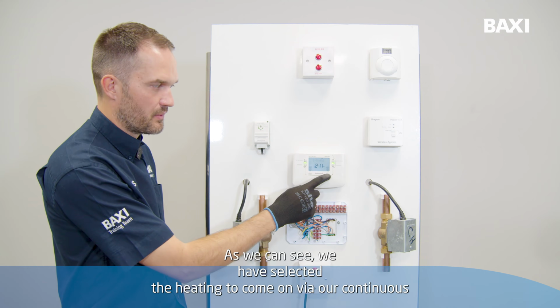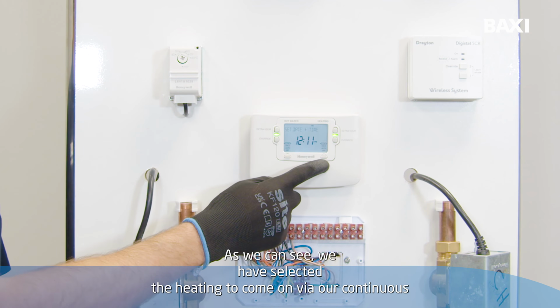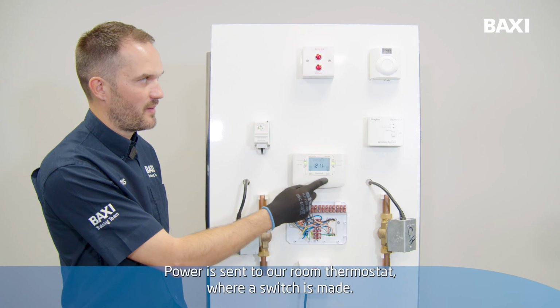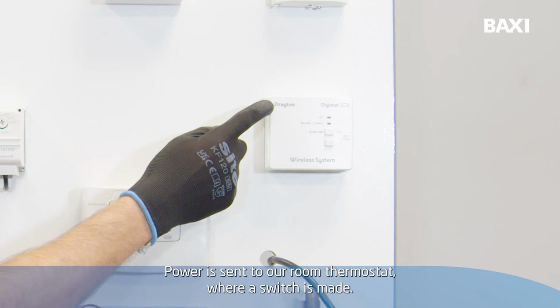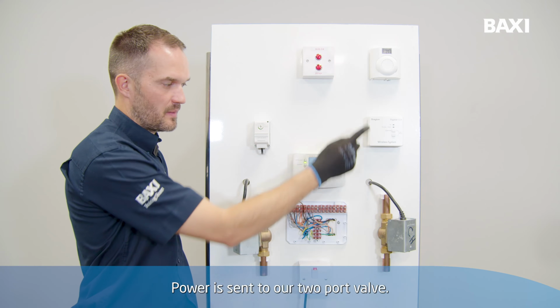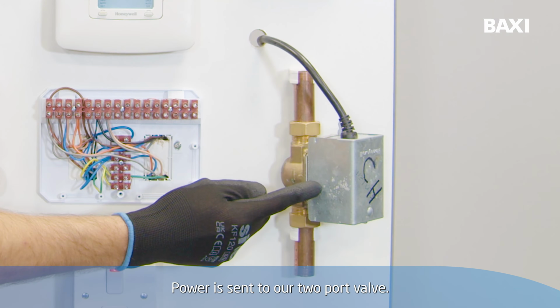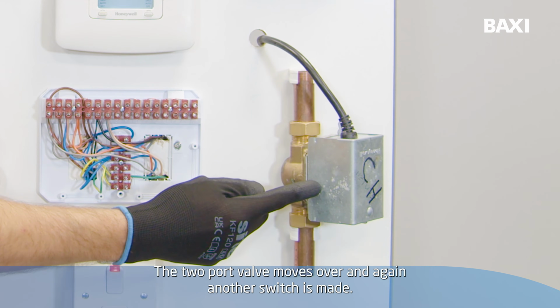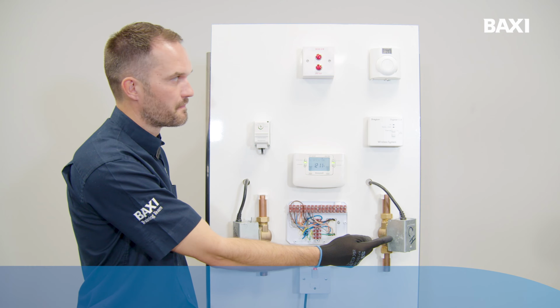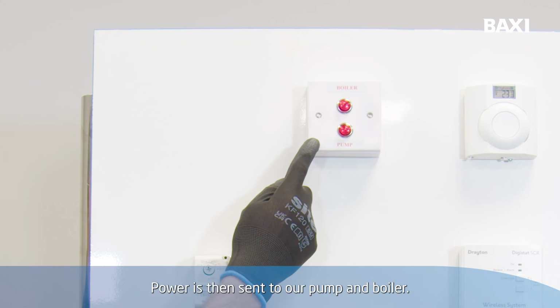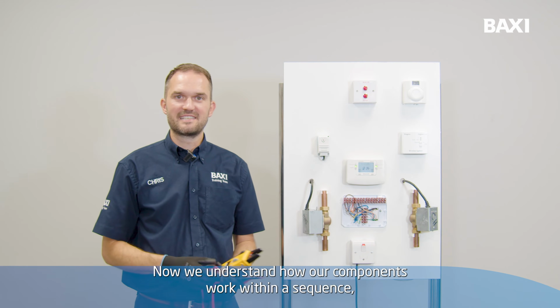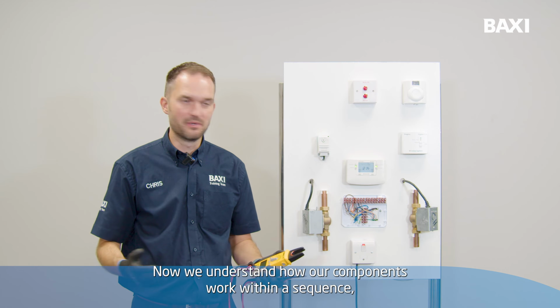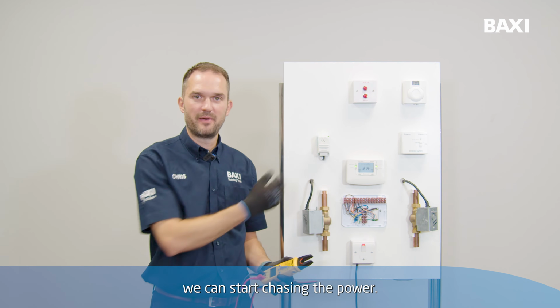As we can see, we have selected the heating to come on via our continuous button. Power is sent to our room thermostat, where a switch is made. Power is sent to our 2-port valve. The 2-port valve moves over, and again, another switch is made. Power is then sent to our pump and boiler. Now we understand how our components work within a sequence, we can start chasing the power.